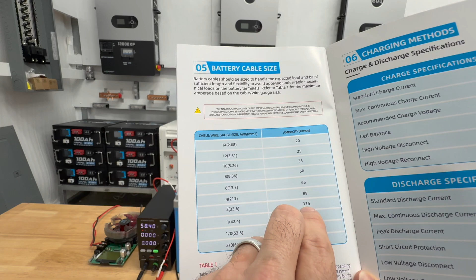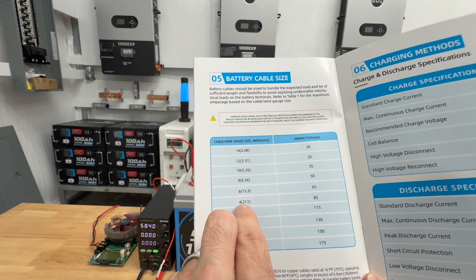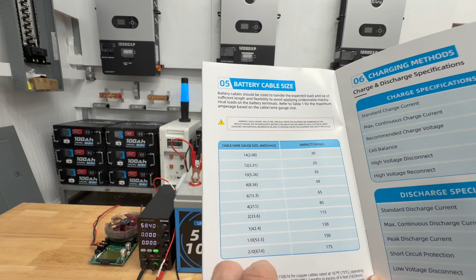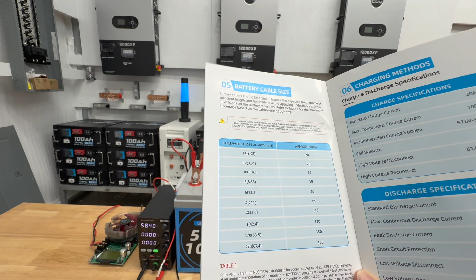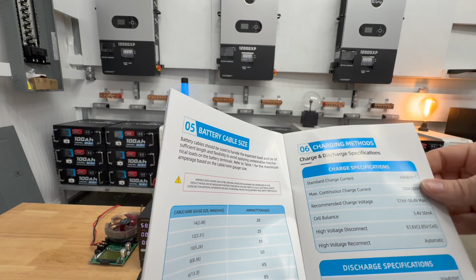So if you're going to say you're going to pull 100 amps, 115 amps or less out of it, use 2 gauge wire. If you're going to do a lot less than that, you could probably get away with 4. I never recommend going with 6 or 8 gauge. It's just too thin. So I'll use 2 gauge when this is hooked up to my system, and then I'll have a fuse set up, either 125 or 150 amp T-class fuse, one or the other, but 2 gauge wire, normally what I recommend if you're only trying to get 100 amps or so out of it.